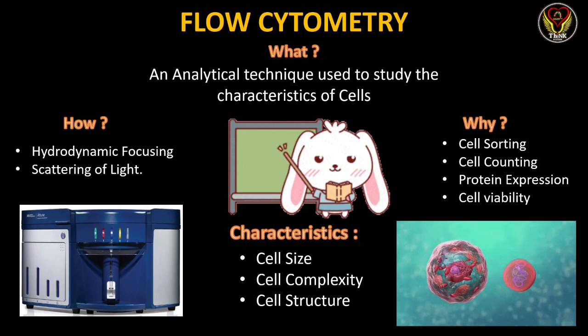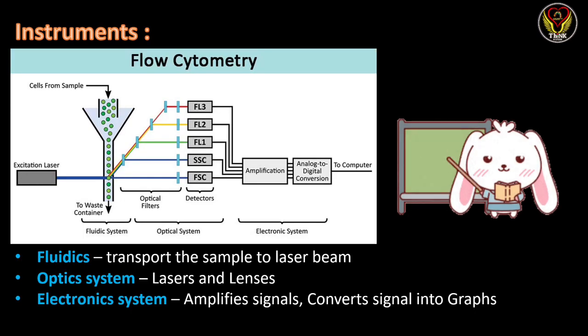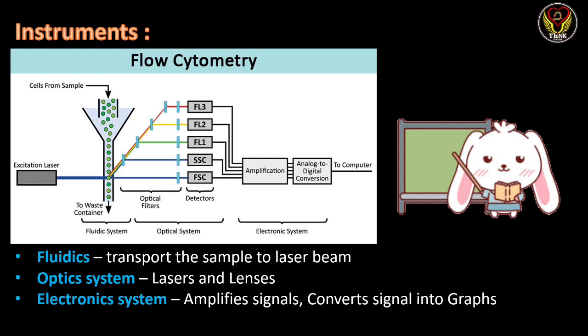How does this technique work? It is based on two major principles: hydrodynamic focusing and scattering of light. Before going into the working mechanism, let's see the major parts: fluidics, optic system, and electronic system. In fluidics, a liquid plays a major role in transporting our sample to the laser beam. The optic system comprises lasers and lenses involved in the analysis. The electronic system receives signals from the optic system, amplifies them, and converts the amplified signals into graphs which can be interpreted by us.